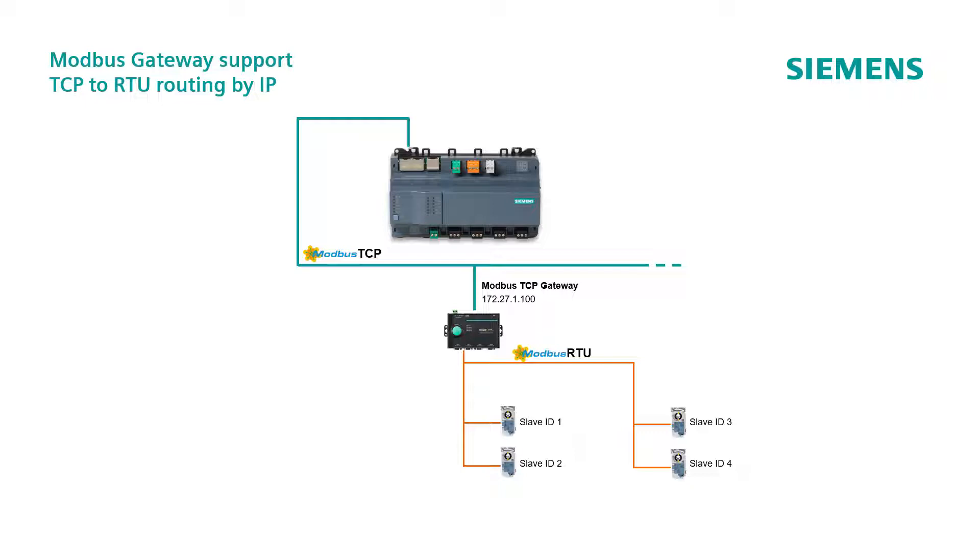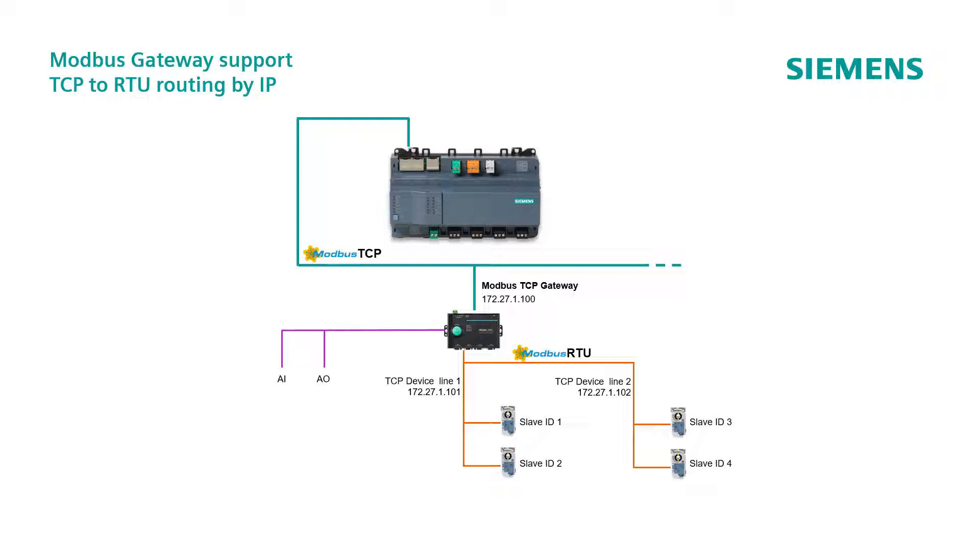At the same time, some Modbus gateways can also carry data points too, independently from the RTU device lines. The line 1 gets the IP address 172.27.1.101, while the line 2 gets the address 172.27.1.102. Let's see how to configure this example in ABT site.